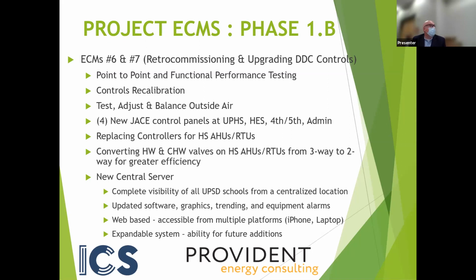The second takeaway is we're going to be installing brand new controls hardware. As you can see, that's the fourth bullet down: 4 new JACE control panels at the high school, elementary school, 4th/5th building, and admin building. We're going to be replacing controllers in the high school on the air handling units and rooftop units. Existing controllers are probably 15 years old, and in the controls world, that's pretty much a dinosaur.